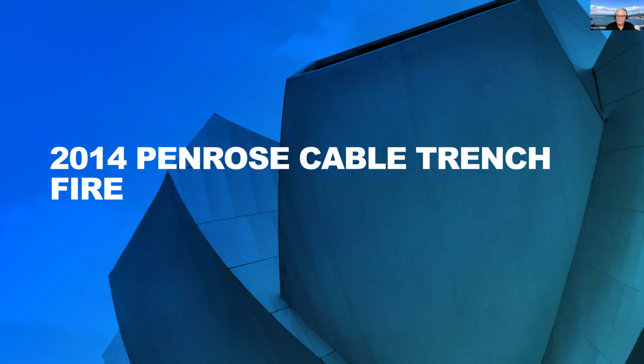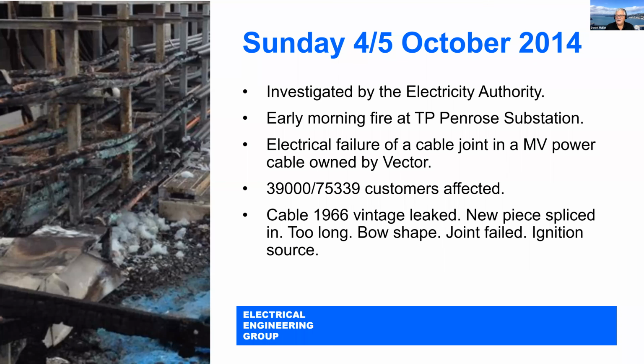There was a fire in 2014 in Penrose, also investigated by the Electricity Authority. Early morning, I think it was a Sunday, a fire started due to failure of a medium voltage power cable owned by Vector, which ran into the cable duct in the Transpower substation. 39,000 customers were affected, but they had to switch off power to work on or extinguish the fire, so eventually over 75,000 people were affected.